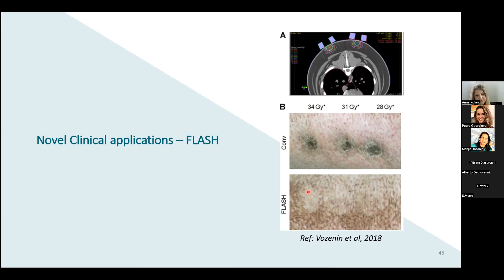Flash requires very high dose rates, of the order of 40 to 200 gray per second. For a cyclotron, to achieve such intensities and dose rates, it has to run at its maximum energy, because when you go down with energy, you have to use degraders, and that drastically reduces the intensity. So to deliver flash with the cyclotron, techniques such as so-called transmission beams have to be used, where you place the Bragg peak outside of the target, what we see here on the far left, and the target is treated in the beam plateau. For light, because we change the energy electronically, we don't use any degraders, and the intensity is invariant on energy. So we keep the same intensity, meaning we could plan for flash placing the Bragg peaks inside the target like you would normally do with pencil beam scanning.